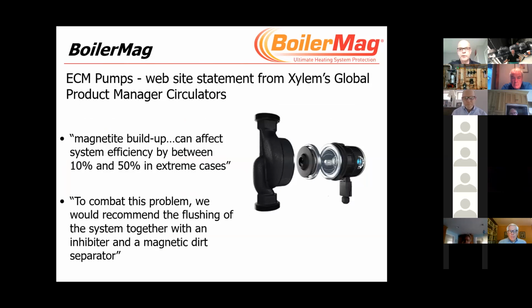So I know you're all familiar with Xylem and B&G and the EcoCirc circulator. This is what it says on the Xylem website: magnetite buildup can affect between 10 to 50% of efficiency. To combat this problem, we recommend flushing of the system together with an inhibitor and a magnetic dirt separator.